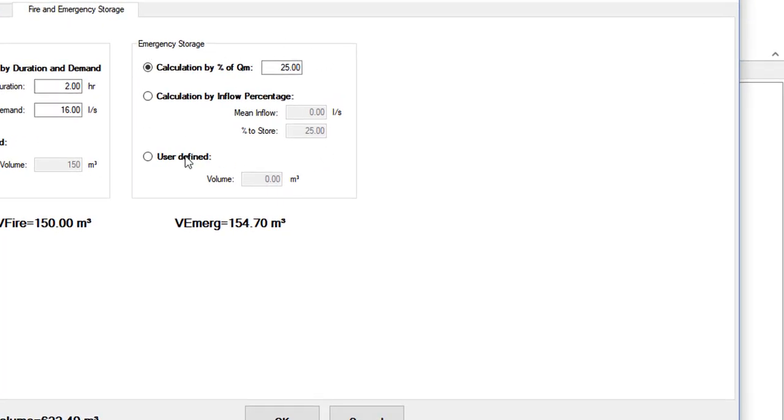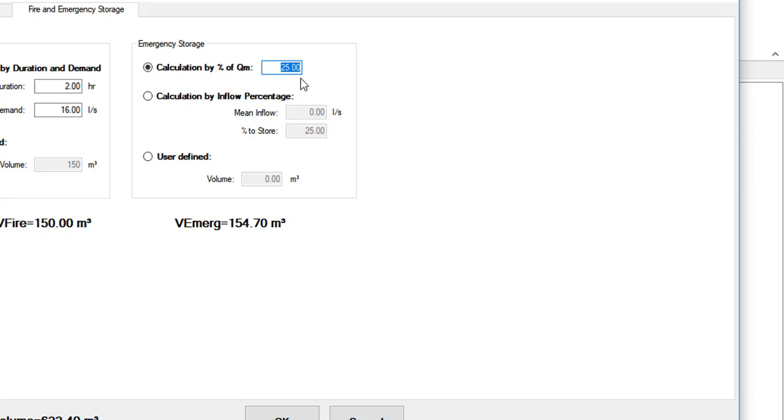Then, to the right, we have the box with options to consider emergency or contingency storage, such as faults in the supply to the tank. In this case, we have three options. The first one allows you to calculate the storage as a percentage with respect to the water network mean demand. The second considers that the volume is obtained as a percentage of the mean inflow to the storage tank. This would be the case in tanks supplied from pumping stations where, because of their vulnerability, there could be mandatory a storage calculated as the percentage of the mean daily pumped flow.